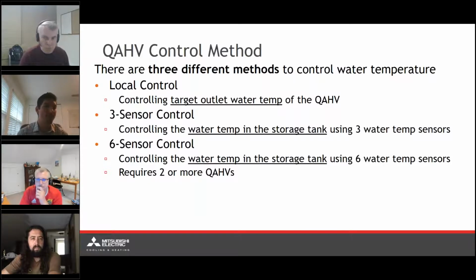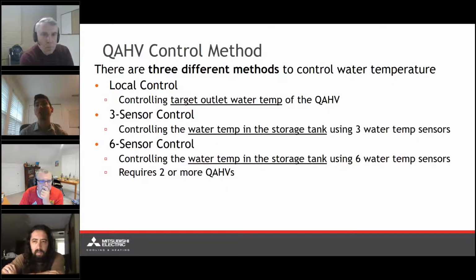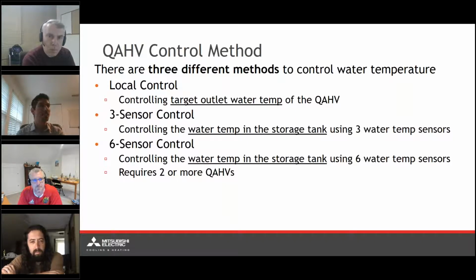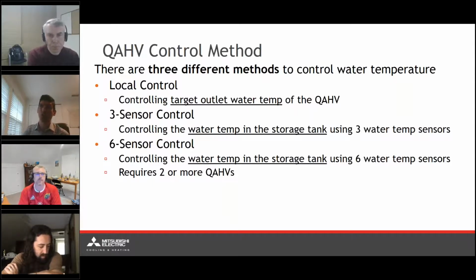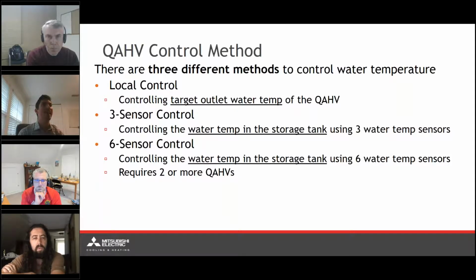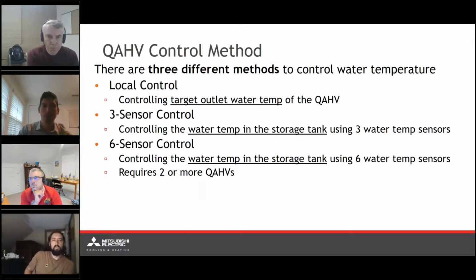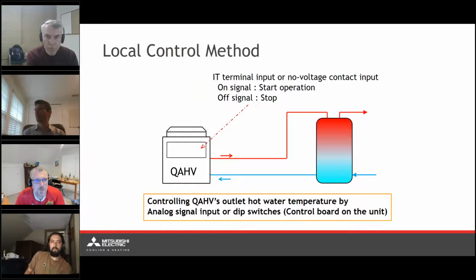So we have 3 different methods that we could use to control the water temperature in a QAHV. We have a local control option. This is not recommended, but this is controlling to the target outlet water temperature of the QAHV. I say we don't recommend this because we want to ultimately be designing the QAHV for maintaining an adequate amount of water in storage tanks. So we have the 3 sensor control, which is what we saw in the previous schematic, utilizing 3 separate water temperatures. But we also have a 6 sensor control option, which is when we're twinning together multiple of the condensing units. And by using 6 different water temperatures, we're going to have a lot more precise control and cycling on and off of the QAHV as needed, as demand is calling for. So just showcasing the different methods with which we can control.